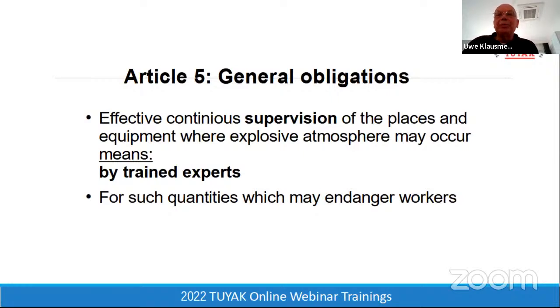Then what we have to talk about is effective continuous supervision of the places and equipment where there is explosive atmosphere. The situation in a factory that's new today is old and used tomorrow. Therefore what we need is supervision at a sensible frequency - each year if it's high risk, then each month, or if it's a pump that's always broken or doesn't work, then every day, or you have a control system that tells you at a certain point that a pump is not working. That's the exercise you have to make here.